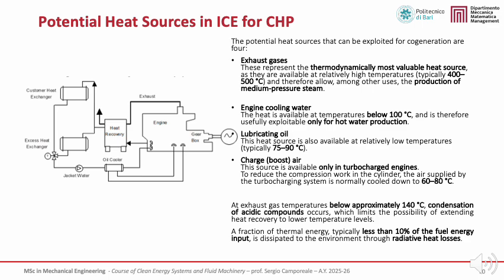A second relevant heat source is the engine cooling water, also known as jacket water. In this case, the heat is available at temperatures below 100 degrees Celsius and is therefore mainly suitable for hot water production and low-temperature thermal uses. Additional heat can be recovered from the lubricating oil cooling system. This heat is also available at relatively low temperatures, typically between 75 and 90 degrees Celsius, and is usually combined with jacket water heat in practical CHP installations.